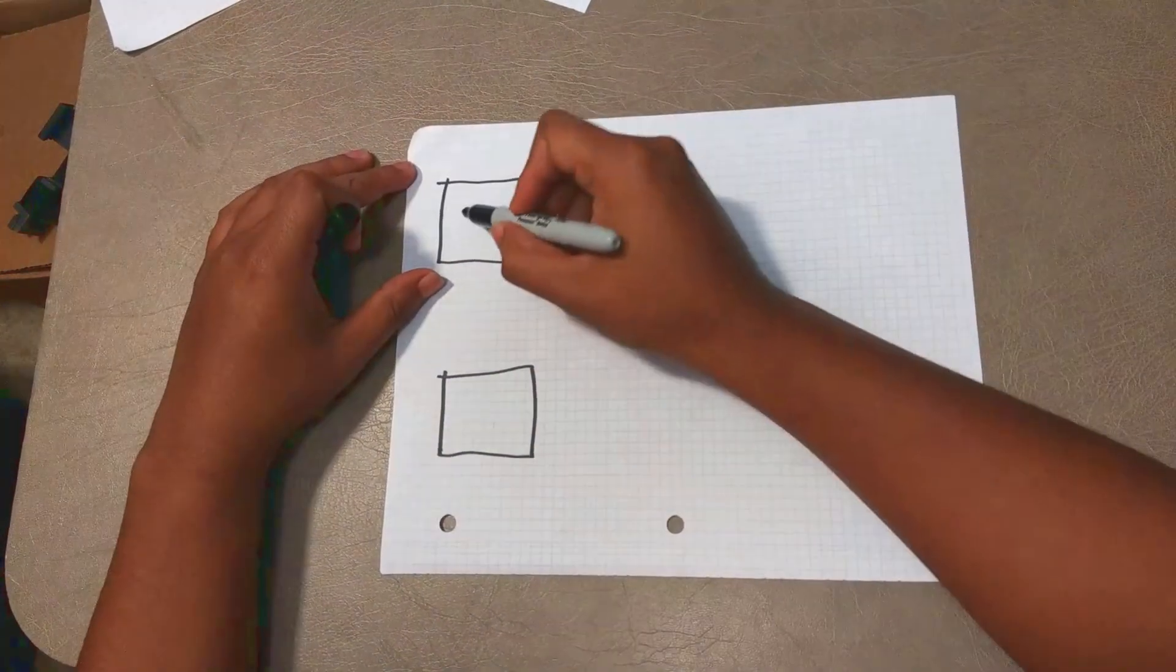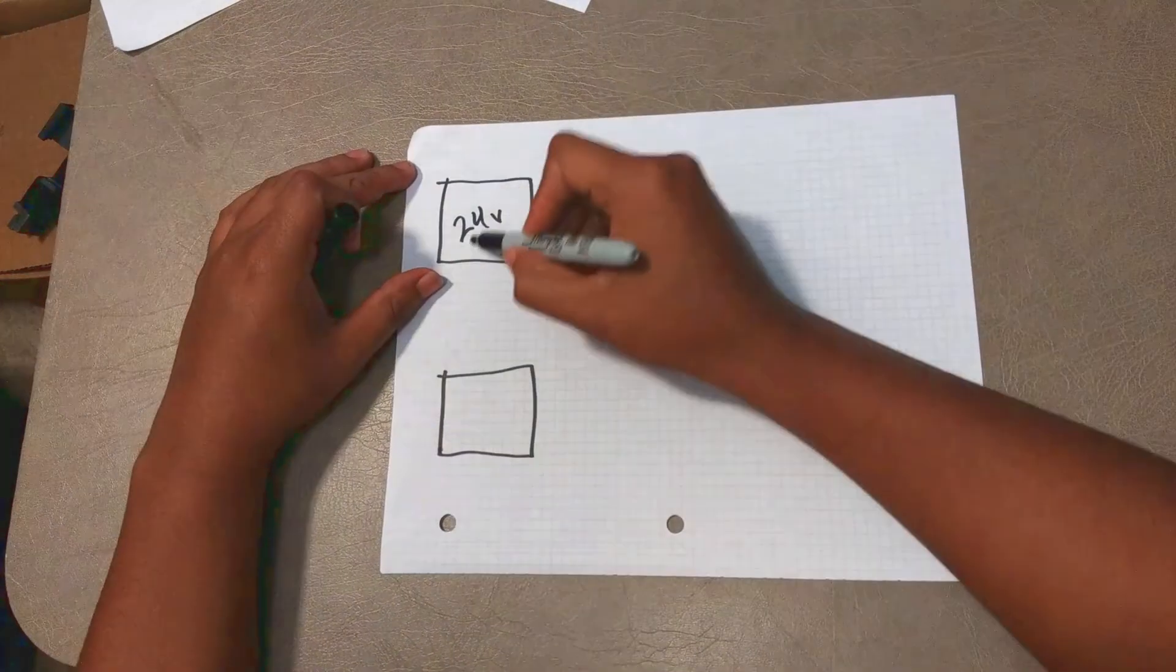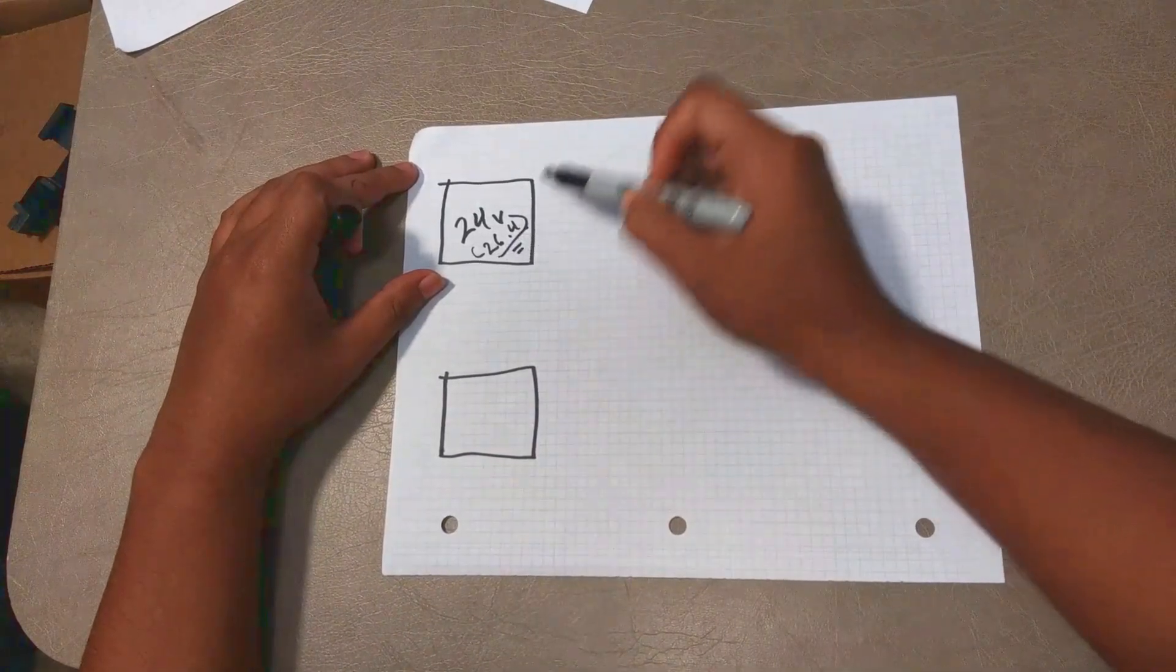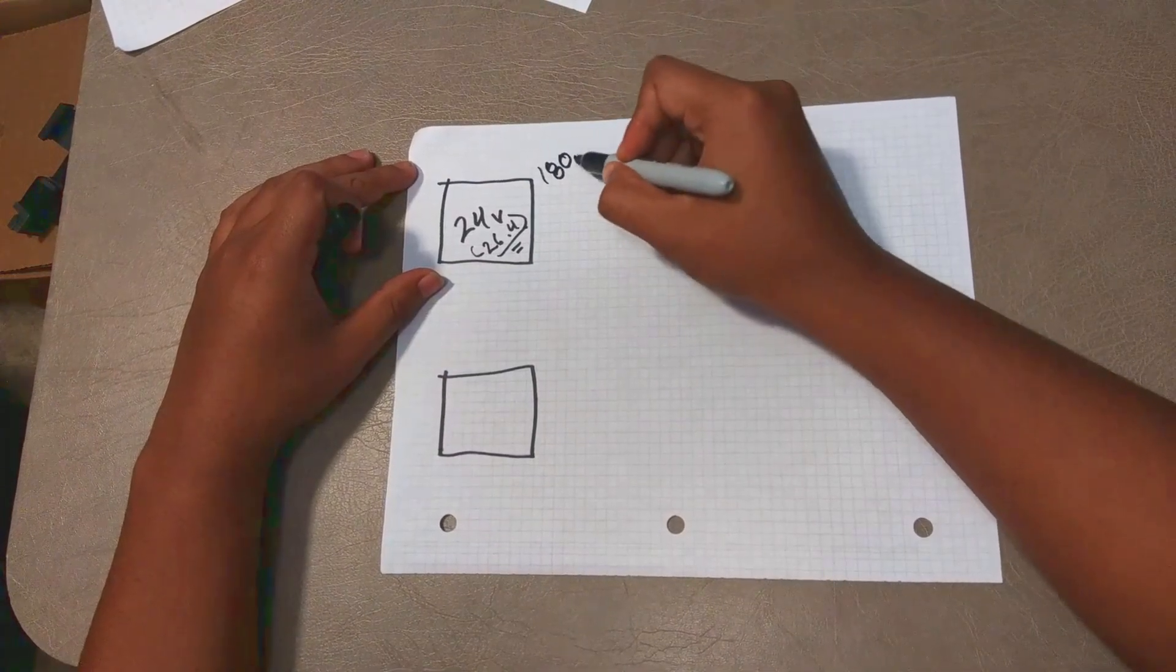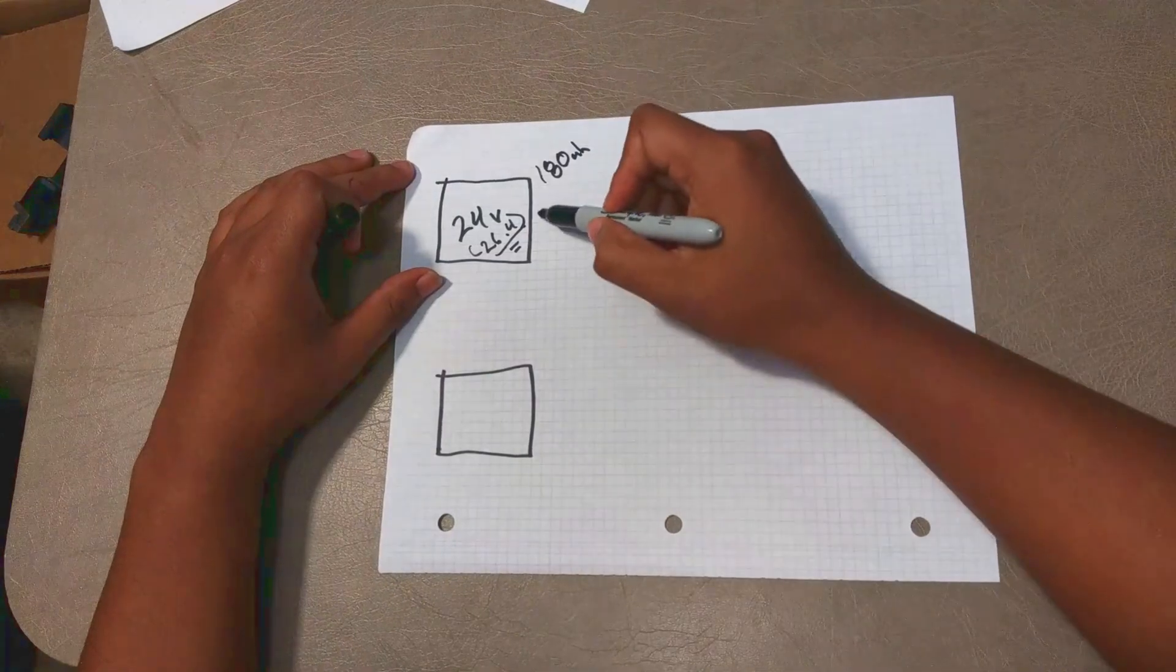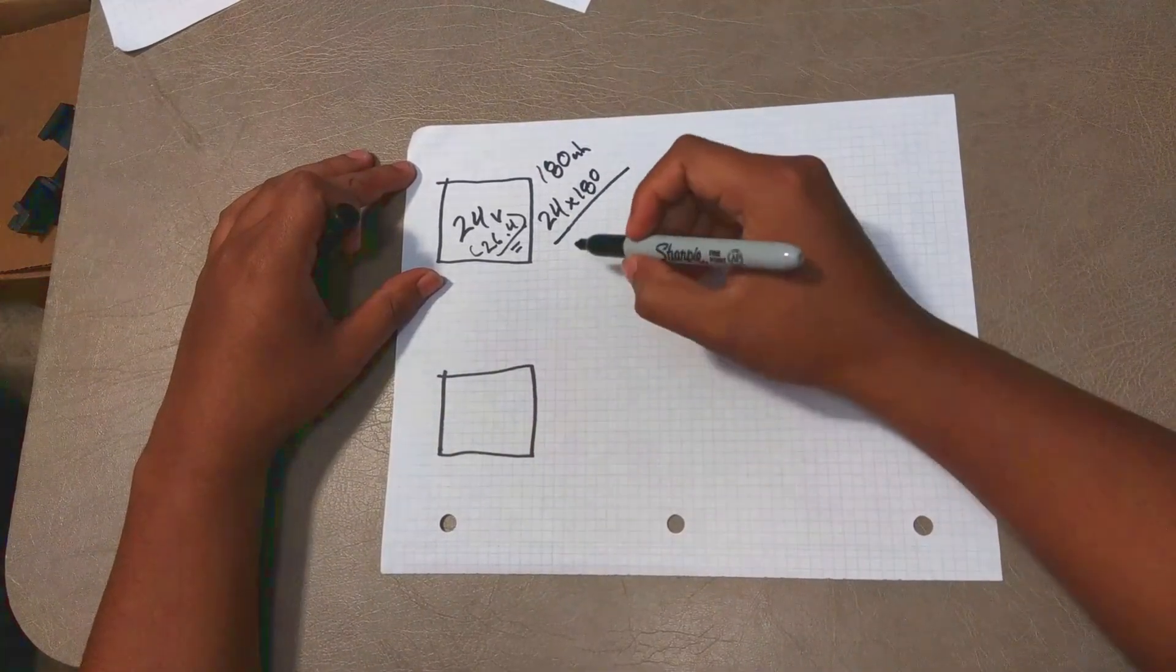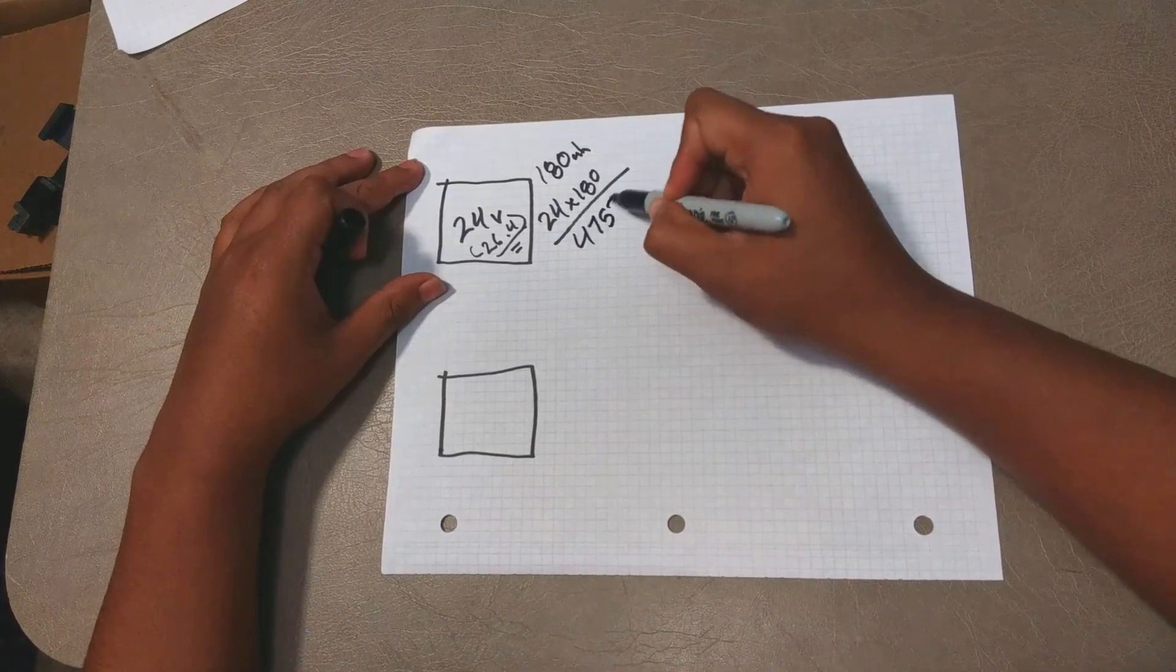So in our case we have a 24 volt system with a nominal voltage of 26.4 which is the actual usable energy inside this battery and it has 180 amp hours. So once you have these two pieces of information you can multiply your voltage by your amp hours and it'll give you the total amount of watts inside this battery. So in our case the total amount of watts is 4752.